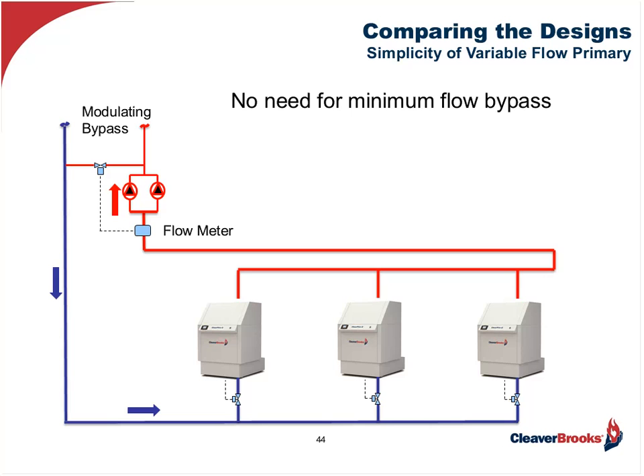I think this came from the chiller side. I first started doing variable flow primary when I was designing chiller systems. And of course, chillers are very much different than high mass boilers. They require a very high minimum flow, and we needed a modulating bypass and flow meter. Boilers, that's not needed. So while you can put it in, it's just an added cost and complexity that's not needed.